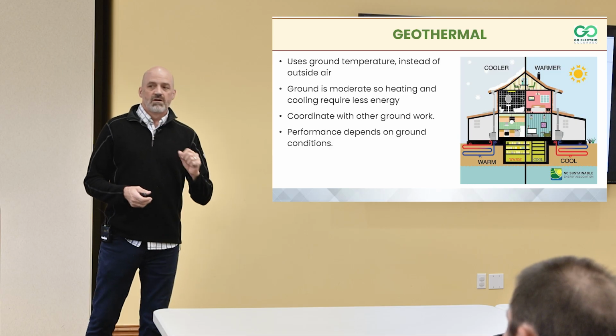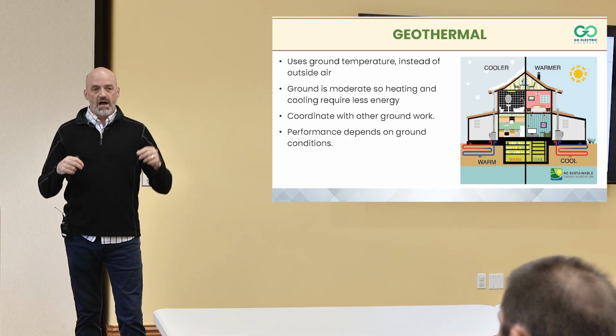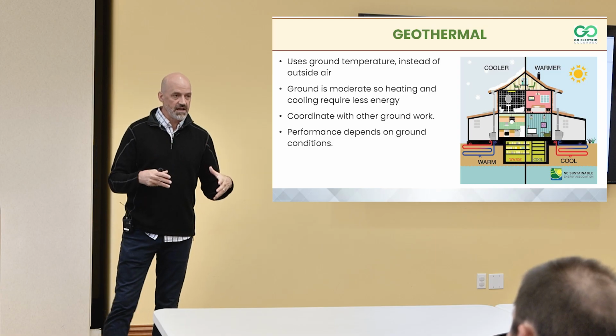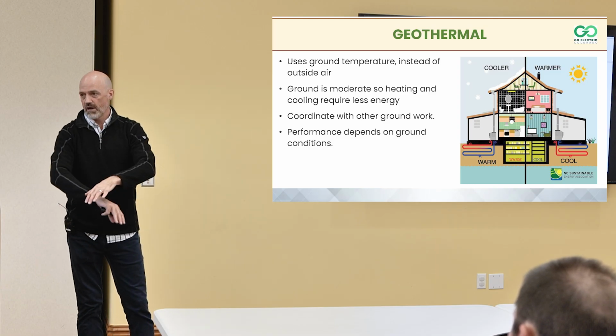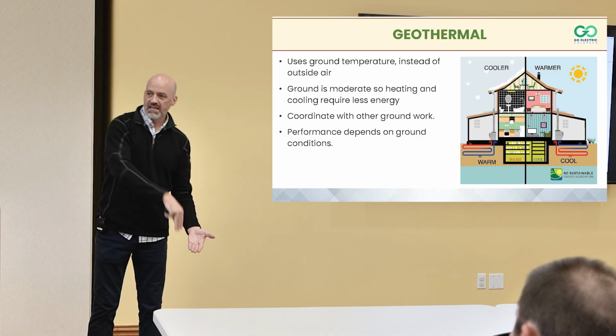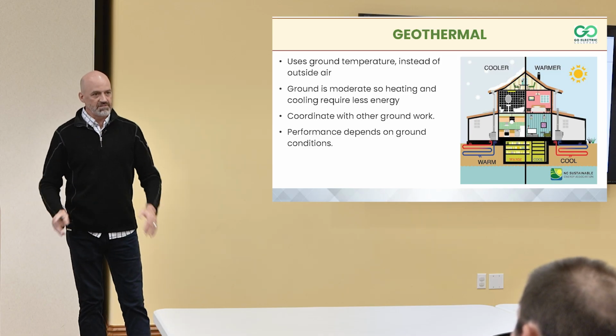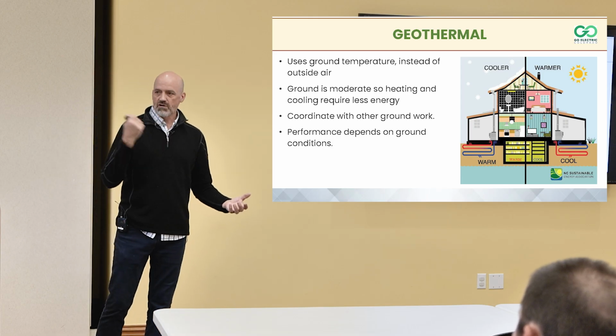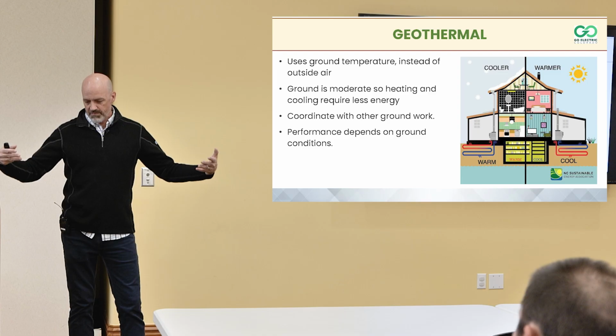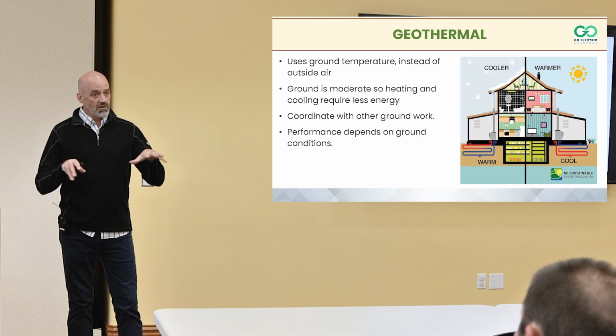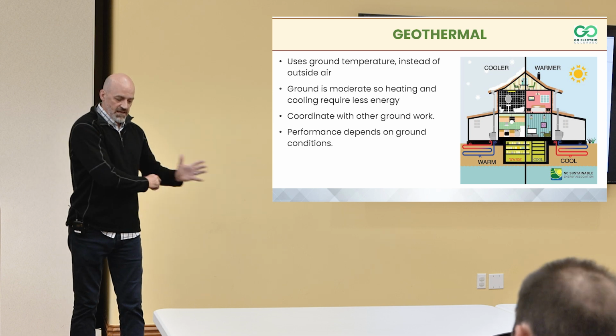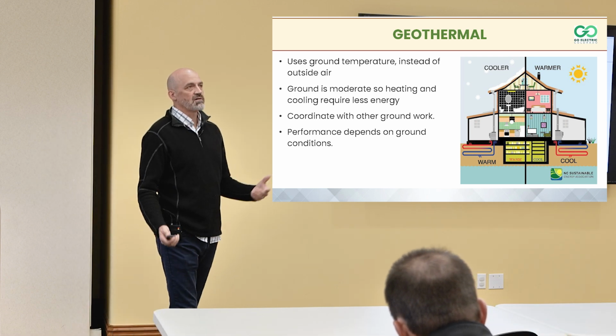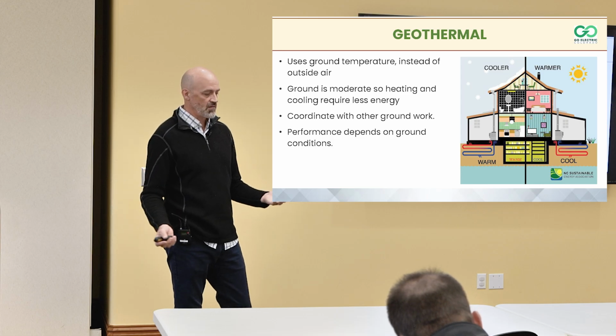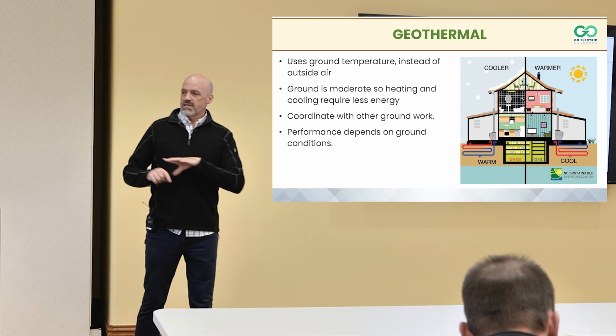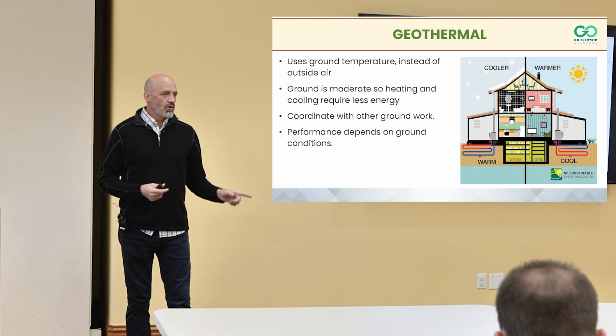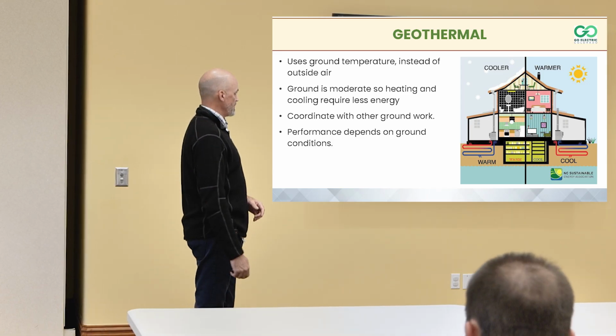I would avoid very dry ground with this, because when it's very dry, you're going to pull out more heat from that ground loop array than you can put back in the summer. There's a lot of ground, and if it's dry, you're effectively overdrawing heat since it gets replaced slowly. If you've got fairly wet ground, that's a great opportunity because that heat is transient - it'll be replaced regularly, and you probably won't be overdrawing that loop field throughout the season.